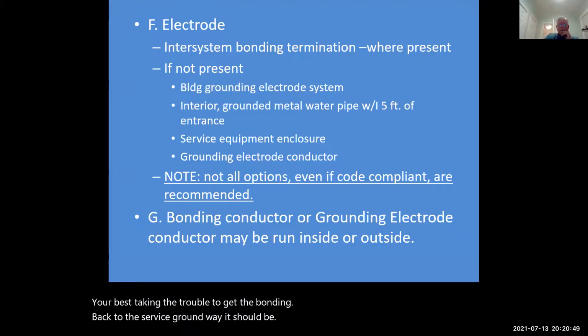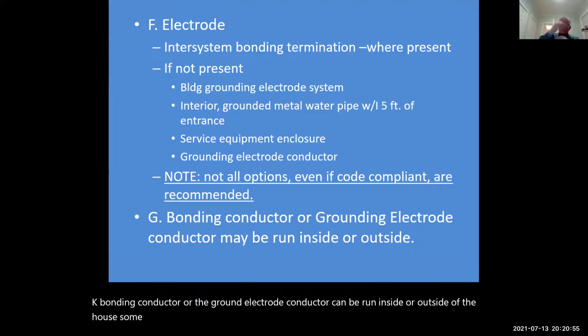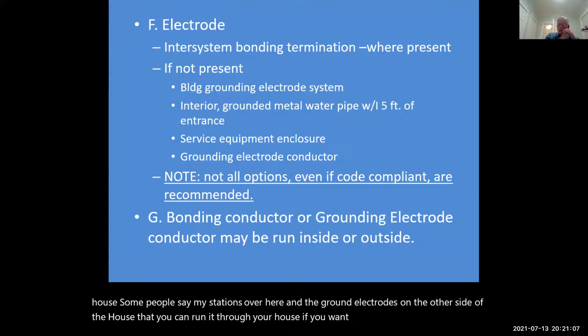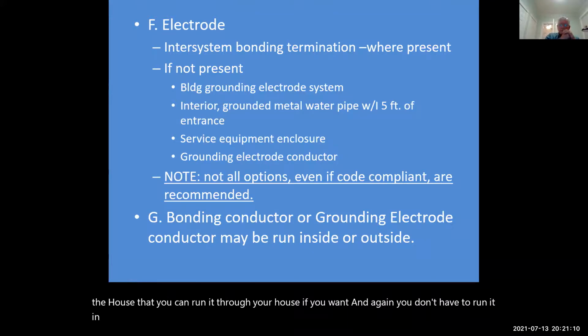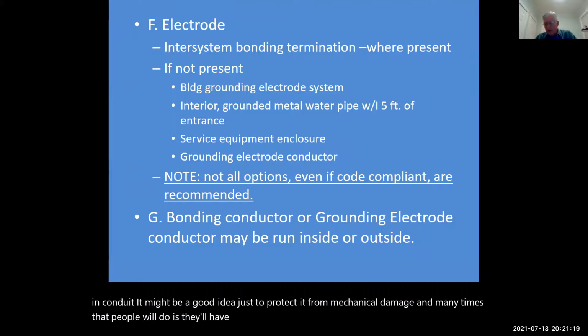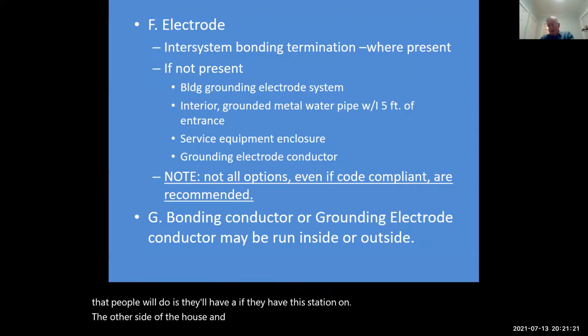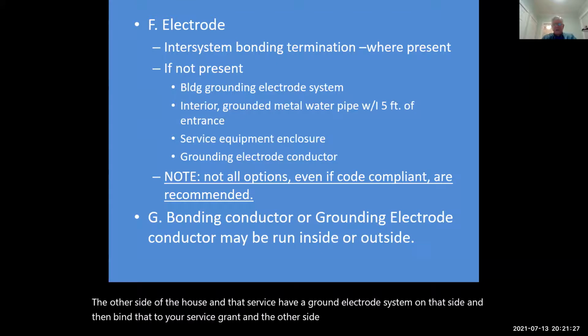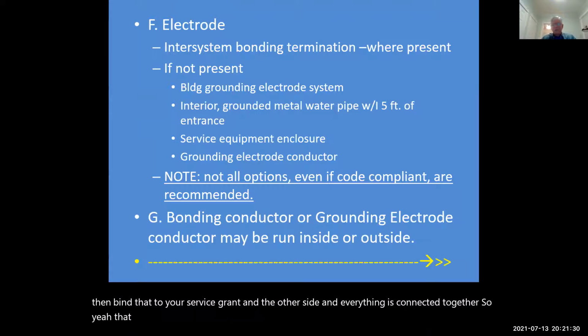A bonding conductor or the ground electrode conductor can be run inside or outside of the house. Some people say, well, my station's over here and the ground electrodes are on the other side of the house. You can run it through your house if you want. And again, you don't have to run it in conduit. It might be a good idea just to protect it from mechanical damage. And many times what people will do, if they have the station on the other side of the house, is have a ground electrode system on that side and then bond that to their service ground on the other side, and everything is connected together. So yeah, that's the equal potential connection.